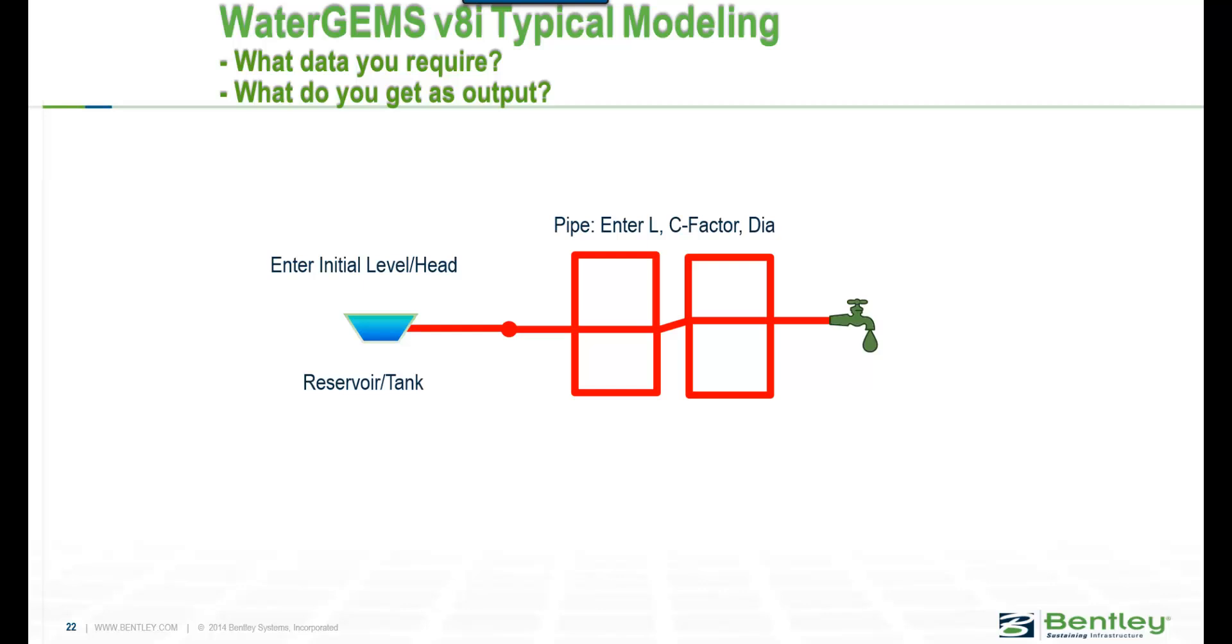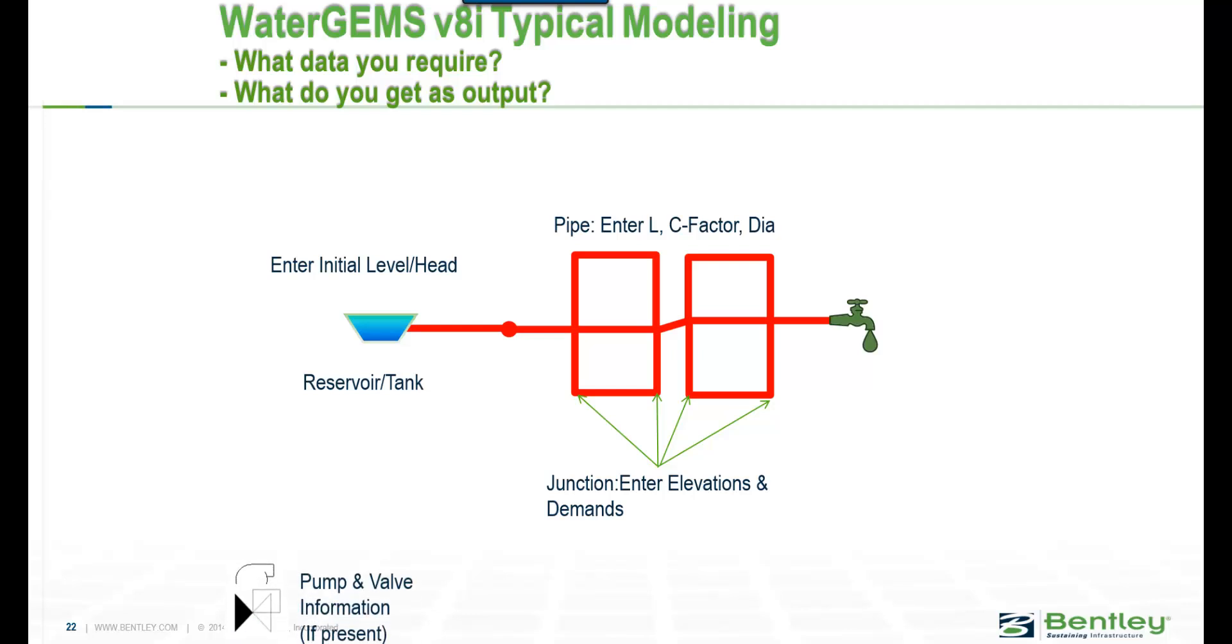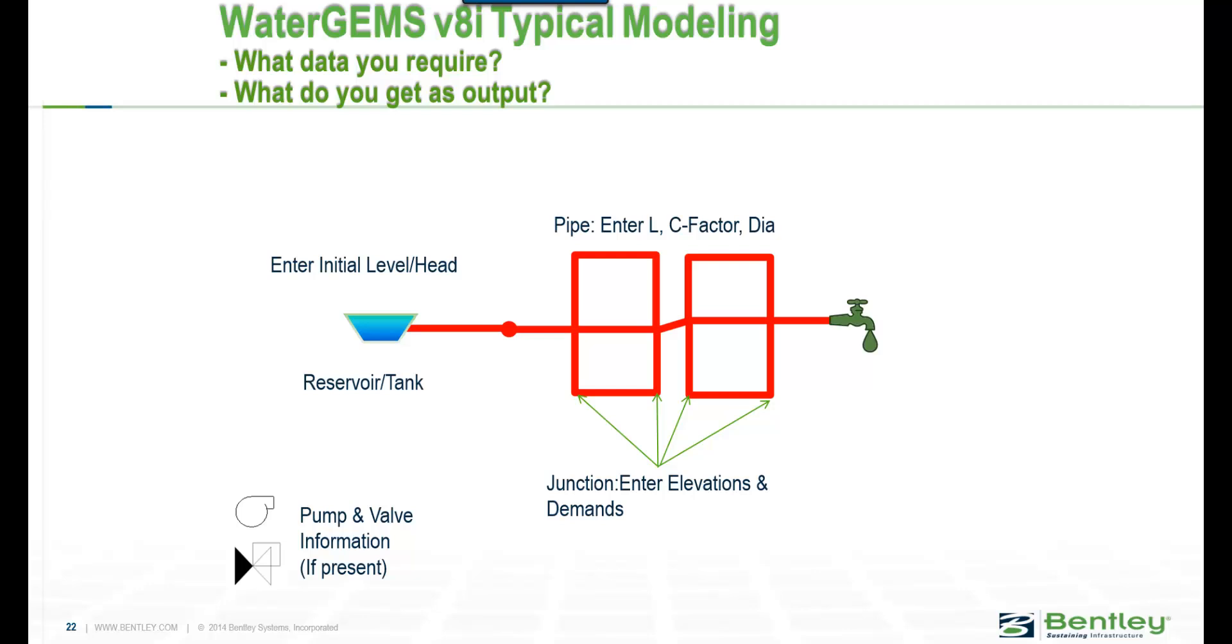For the pipes, you need to enter your length, your C factor, and your diameter. For your junction nodes, you need to enter your elevations and demands, and then if there are pumps and valves present, you need to enter that. These are the minimum data required to do a simple model.